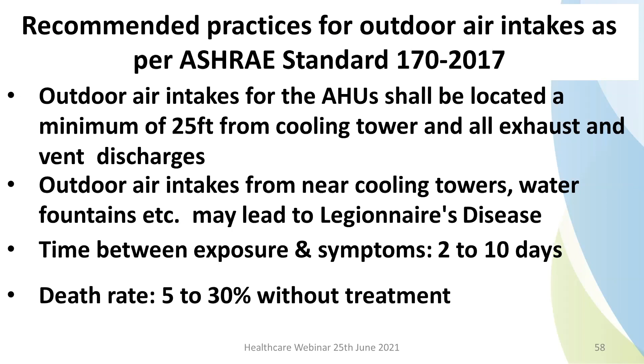Fresh air and exhaust. Outdoor air intakes for the AHU shall be located 25 feet away from the cooling tower. We talked about Legionnaires' disease and all exhaust and vent discharges. Outdoor air intakes near cooling towers, water fountains may lead to Legionnaires' disease. The time between exposure and symptoms is 2 days. And this we talked about actually. Air intakes are accumulating sites for dirt and debris, including rotting botanical materials such as leaves, which are growth sites for fungi such as Aspergillus fumigatus.